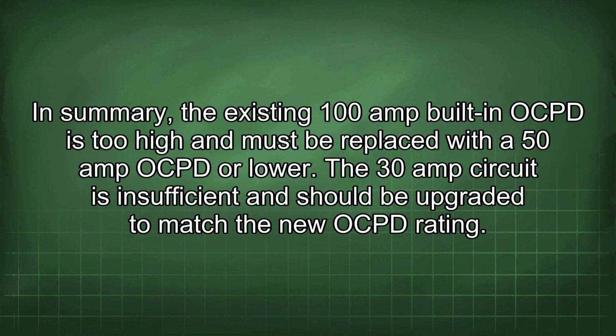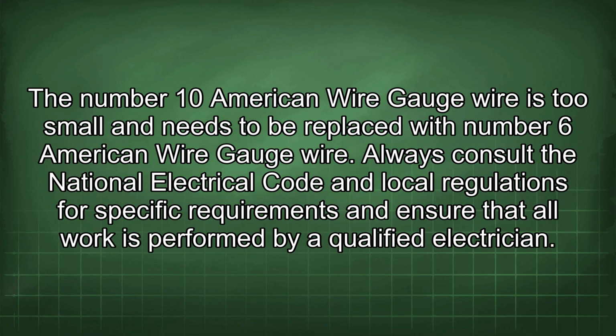In summary, the existing 100 amp built-in OCPD is too high and must be replaced with a 50 amp OCPD or lower. The 30 amp circuit is insufficient and should be upgraded to match the new OCPD rating. The number 10 American wire gauge wire is too small and needs to be replaced with number 6 American wire gauge wire. Always consult the National Electrical Code and local regulations for specific requirements and ensure that all work is performed by a qualified electrician.